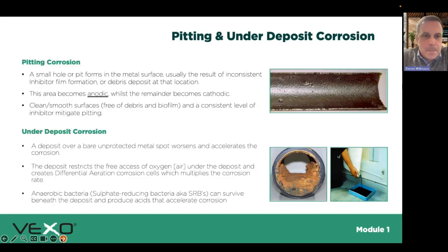Pitting and under deposit corrosion can be very similar in terms of how they look, but pitting corrosion is if you have a dirty pipe work, you're laying down inhibitor and you've got inconsistent film. You have this, if you like, demarcation, where one side is anodic and the other is cathodic, because one side is being protected by inhibitor, the other side is not. And unfortunately, that's where we start seeing localized pitting corrosion on the surface.